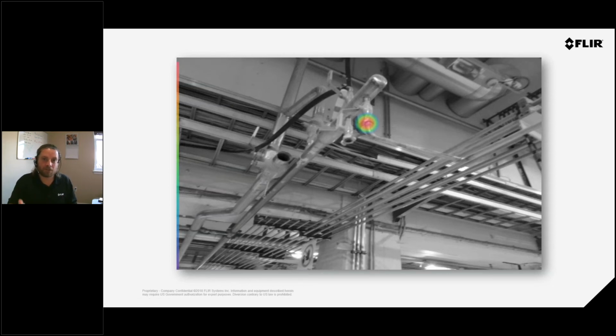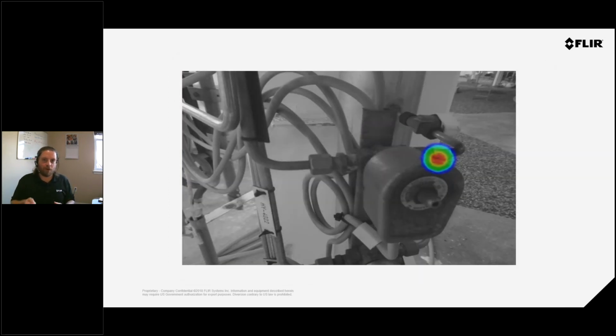So it's easy to check your work. It's easy to give direction to somebody on where they need to go. And it's super easy to operate. All you've got to do is walk around and scan your facility. You don't have to be super close to anything. You don't have to point it right at it. You could be focusing on something a foot or 2 feet to the left, and it's still going to show up, that sound, because we have those 124 microphones capturing a big space. Again, here's another image of just a bad connection. And this is compressed air just leaking out, and again, just dollars coming out of those tubes and pipes.